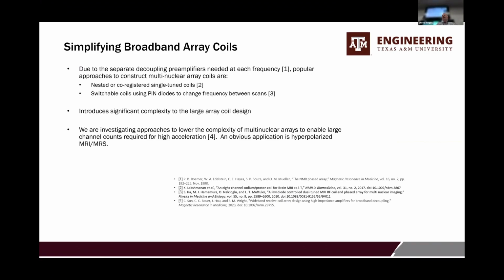So in the remaining 2 minutes, let me just summarize that if you want to do multinuclear, simultaneous spectroscopy, you're going to need array coils. And array coils are complex enough alone. And what people do is if they want to do multinuclei, they essentially take two arrays in general and just stack them on top of each other. There are some cases where they've double tuned the elements. And there's cases where they've used pin diodes to switch frequency between scans. But this introduces significant complexity.